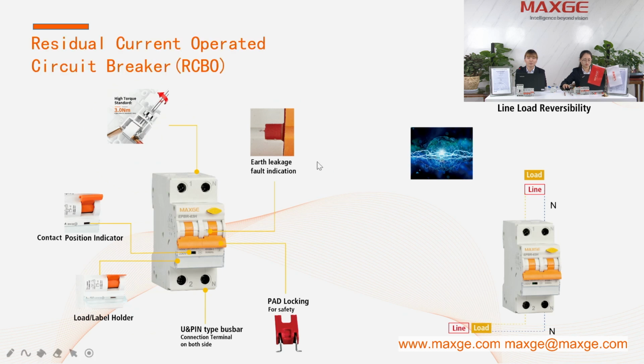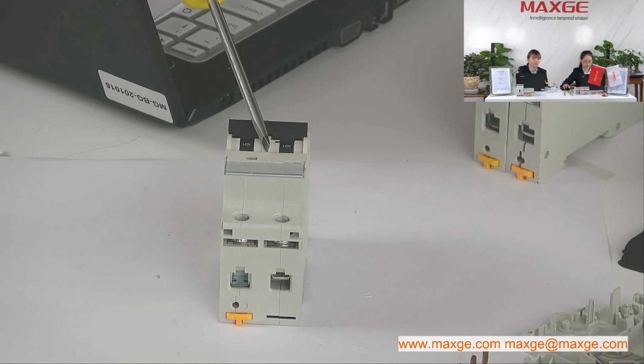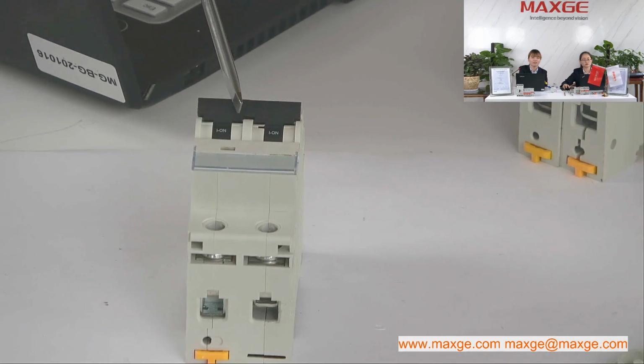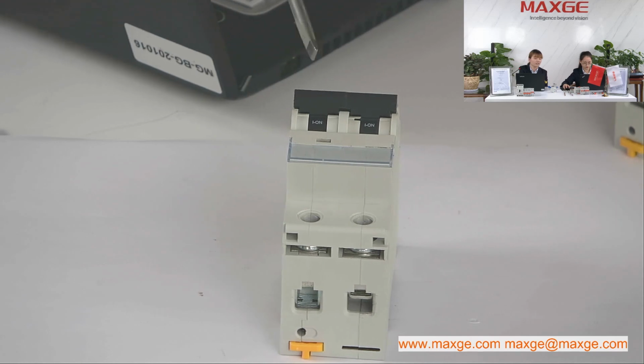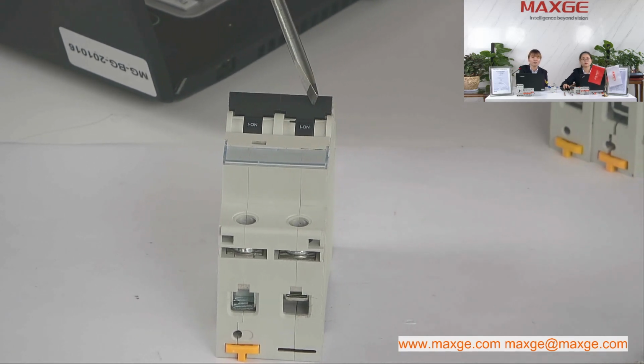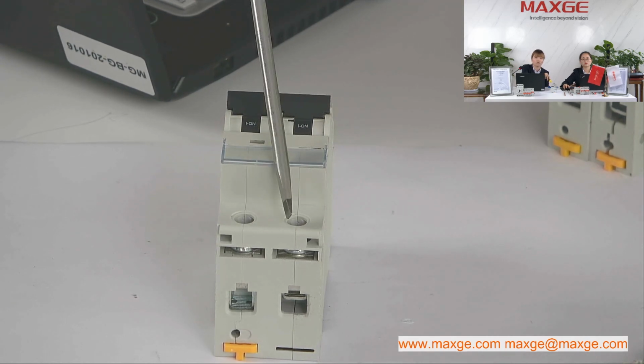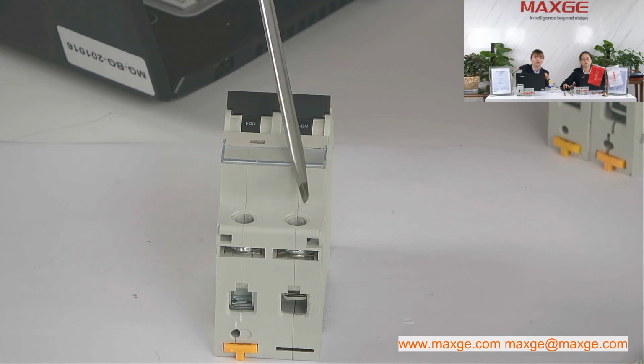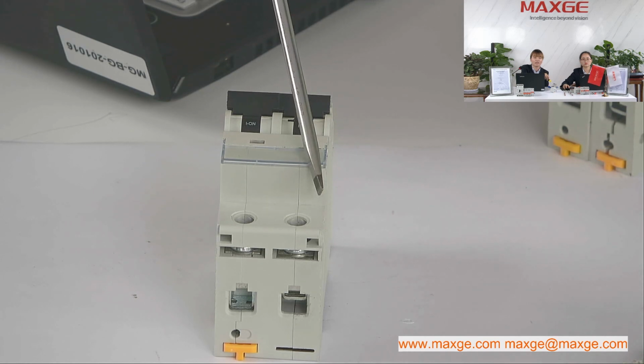Now let me introduce the EPBR-63 series RCBO benefits and features to you. This is a series product in the Alpha series. The indicator, test button and transparent cover are the same design as the RCCB I mentioned before. The special design is for the handle of this type of RCBO. We have designed two separate mechanism parts for the MCB part and the RCCB part. Also, we have made an indicator for RCCB tripping. Also, with safety protection, padlocking with combined head screw, same as RCCB, with high torque 3 Newton. The IEC standard only needs 2 Newton.